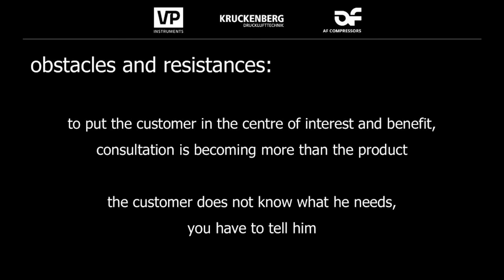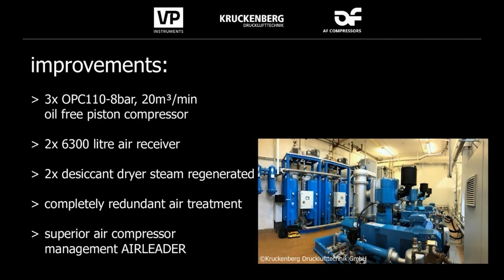Nobody was talking that we changed from refrigerated dryers for most of the production, with just some decentralized desiccant dryers, and we changed the complete system to a complete desiccant dryer system with minus 40 degrees dew point, because they were facing quality problems in the production. So in the end, we realized the solution with 3 times 110 kilowatt, 8 bar, according to ISO 1217, 20 cubic meters output, oil-free compressed air.